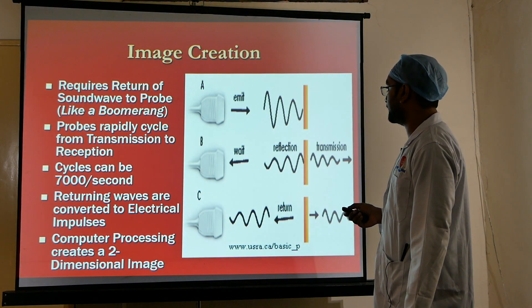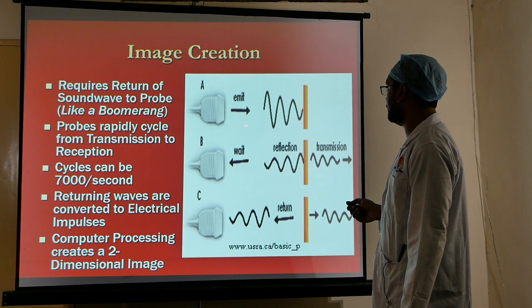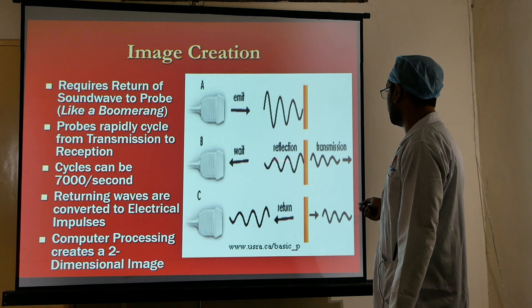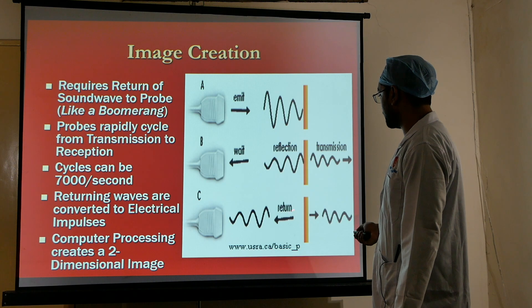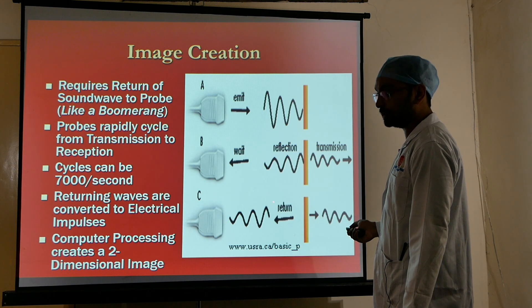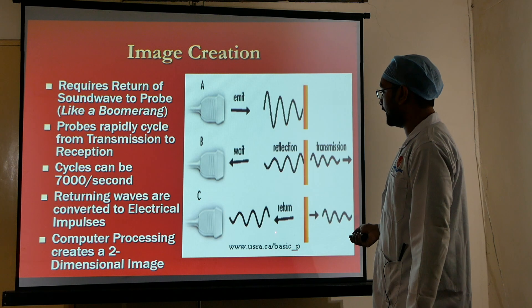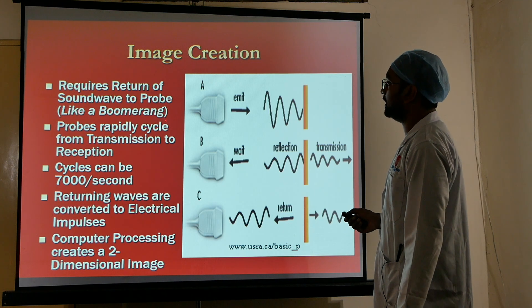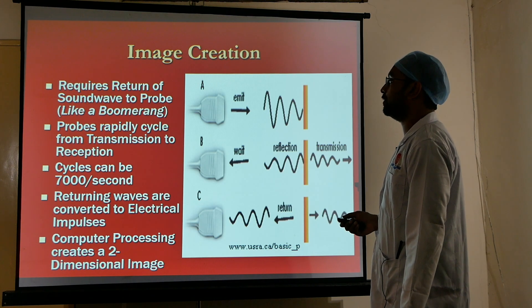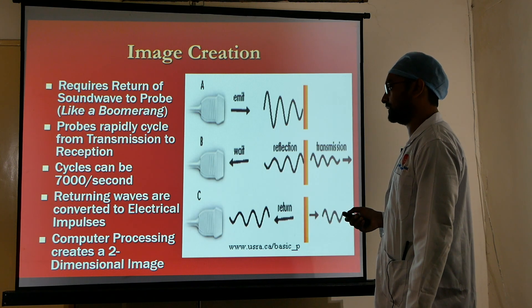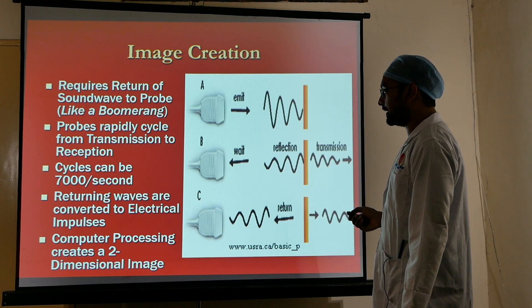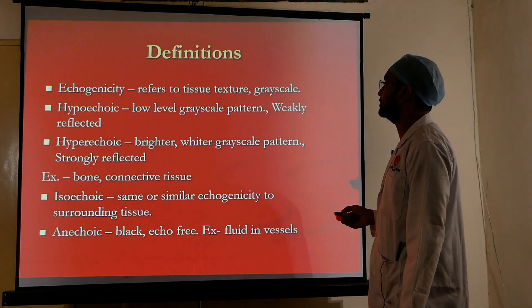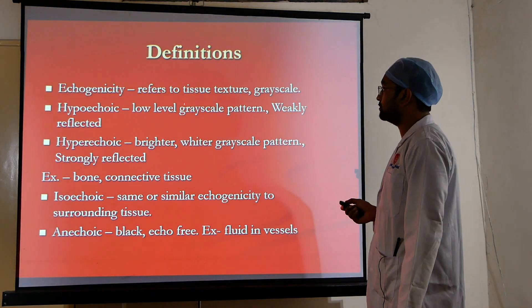The transmitter gives energy to the transducer, which emits ultrasound waves. These waves hit the body surface — some are transmitted and some are reflected back to the transducer. The processor ultimately forms an image. It requires return of sound waves to the probe, just like a boomerang. The probes rapidly cycle from transmission to reception, up to 7,000 cycles per second, and computer processing creates a two-dimensional image.